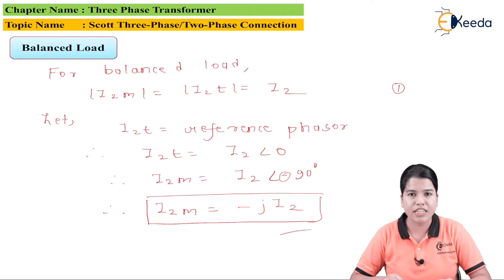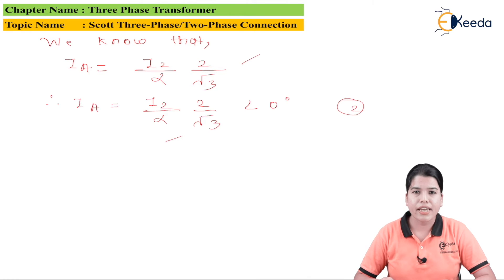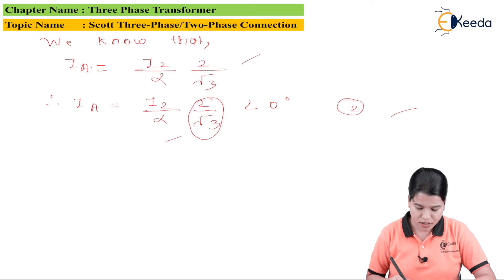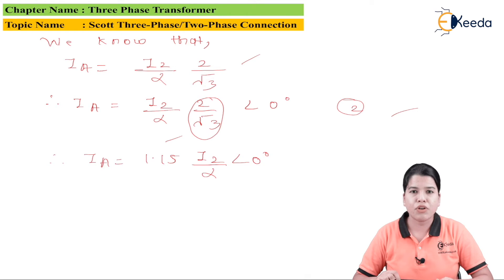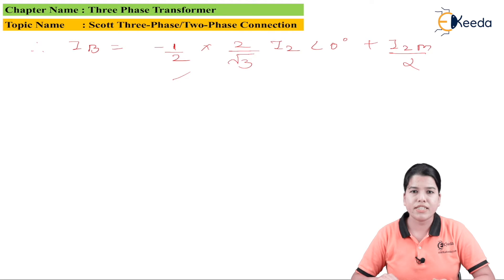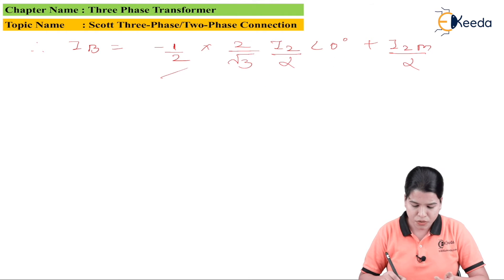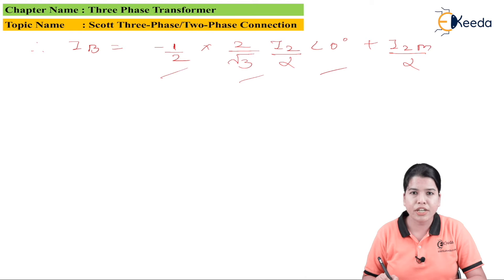The current IA is given by: IA equals I2 divided by alpha multiplied by 2 divided by root 3. In polar form, IA equals I2 divided by alpha times 2 divided by root 3 at an angle of 0 degrees, which equals 1.15 times I2 divided by alpha at an angle of 0 degrees. The formula for IB is: IB equals minus half IA plus I2M divided by 2. Substituting IA: IB equals minus half times 2 by root 3 times I2 divided by alpha at 0 degrees plus I2M divided by 2.